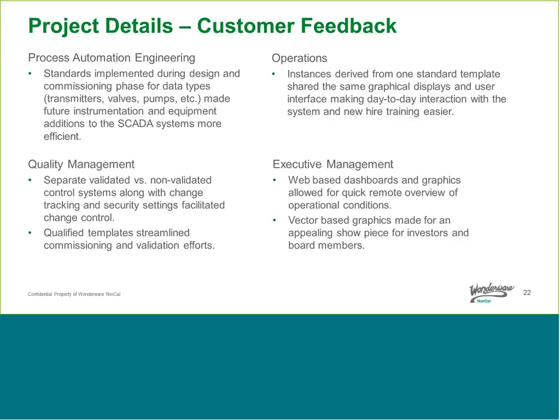The quality management department's biggest win in the design was separating into two SCADA packages: the validated and the non-validated. Anything happening to the HVAC utilities didn't have to go through the stringent change control requirements that applied to the water for injection and environmental monitoring systems. Having those two different SCADA systems and two different historians tracking really streamlined the quality IQ/OQ process, since they didn't have to go through it as intensely for the non-validated system. This allowed them to frequently change what was happening on the utilities and HVAC system without having to go through all those steps.